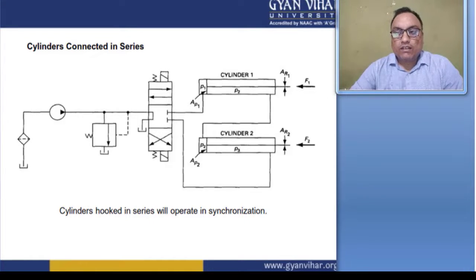Some machines with multiple cylinders require that the cylinder strokes be perfectly synchronized for the machine to operate properly. If all the loads, line sizes and lengths, and friction of the cylinders and machine members are identical, then they may stroke at the same time and rate. While line sizes and lengths and machine loading can be controlled to some extent, friction changes constantly. Thus, when cylinders have to stroke together, use some method to synchronize them.